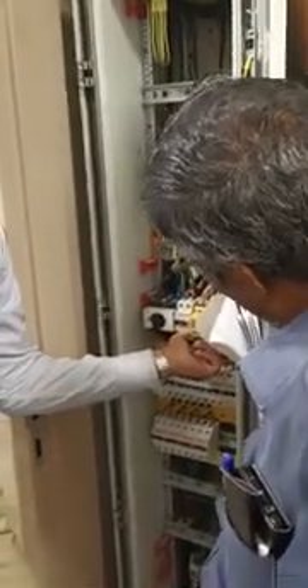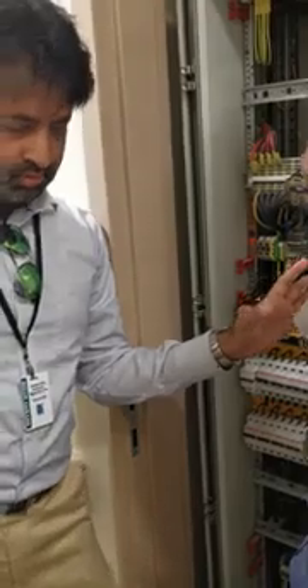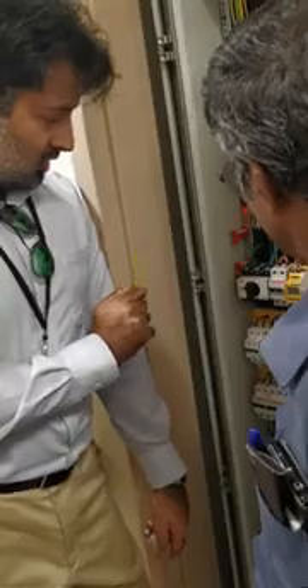This is component number 2, which is called insulation, load and temperature monitor. So the job of this device is to continuously monitor the whole distribution network for insulation resistance, for transformer overload and transformer over temperature. So all alarms coming in the IPS panels are detected and signaled by this particular device. And then this yellow device which you see behind the circuit breakers is the automatic fault locator or automatic circuit locator, because whenever there is a supply circuit failure, this unit detects and signals the number of the failed or faulty circuit, and it displays in all the designated remote stations.